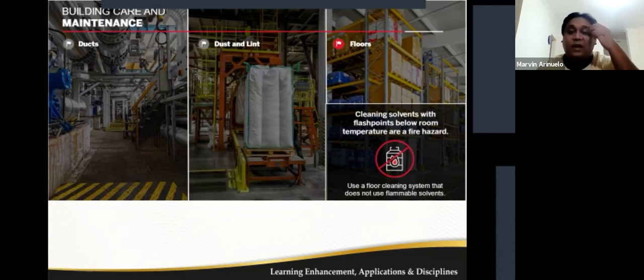And lastly, let's talk about the floors. General care, the treatment, cleaning, and refinishing of floors can present a fire hazard if flammable solvents or finishes are used or if combustible residues are produced. In general, cleaning solvents with flash points below the room temperature are very dangerous to use to clean the floor. Remember this, guys, because we have a quiz. Again, your cleaning solvents with flash points below the room temperature are too dangerous to use to clean the floor.